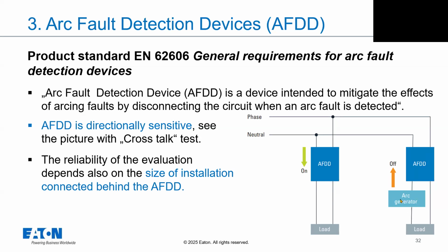But if we use this arc generator on the incoming terminals of an AFDD, like this AFDD on the left side, this AFDD will not switch off. It means the AFDD must be directionally sensitive, and this is also tested: any signal which is coming from the network or from the supply side will not lead to disconnection of the AFDD.